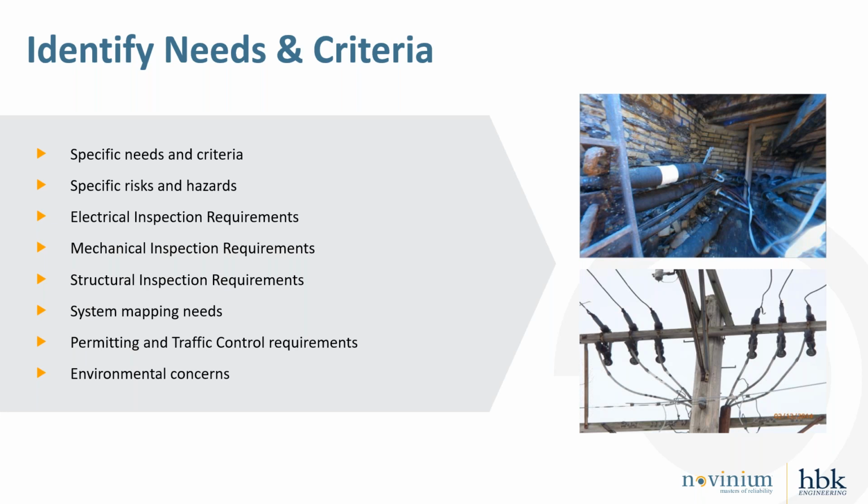But it could also be something as specific as identification that there are terminations on riser poles adjacent to the manholes and that some of those could be deficient, which could also then represent a safety hazard within the structure itself. It's not evident from seeing that within the structure, but it's something that we would plan for in that initial stage.